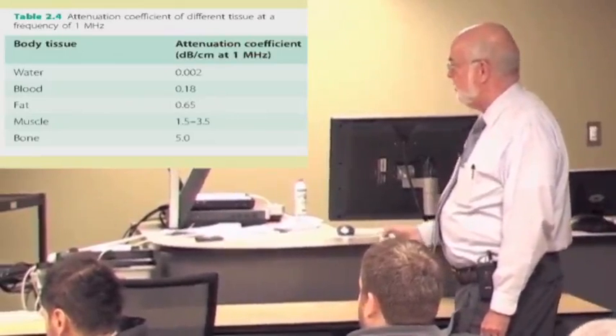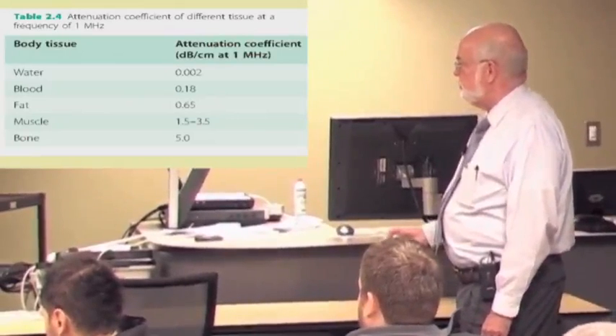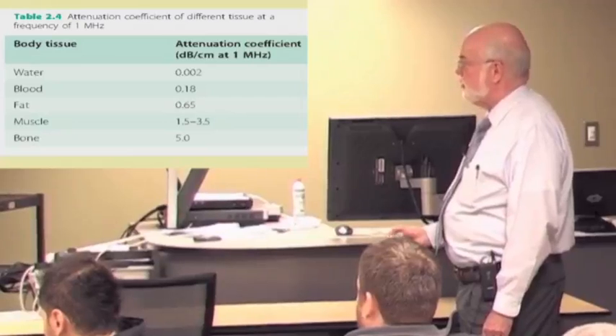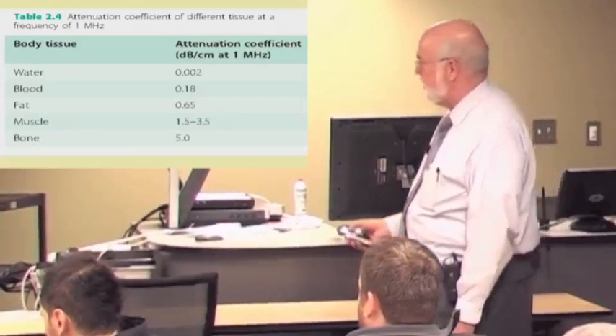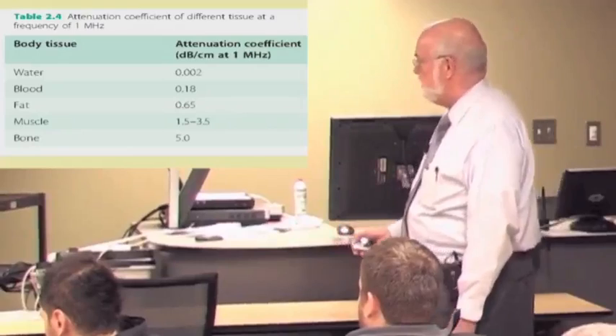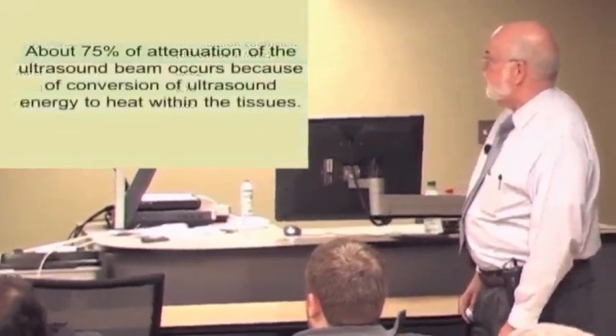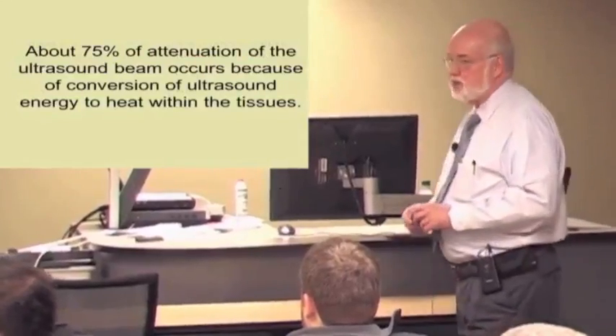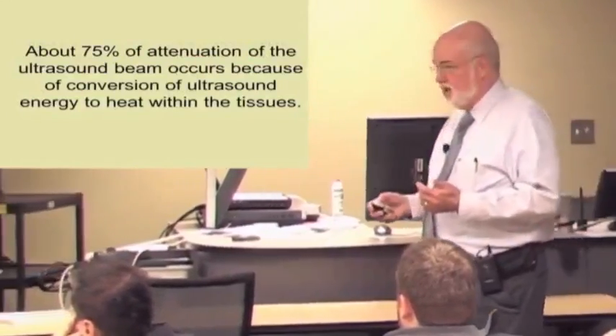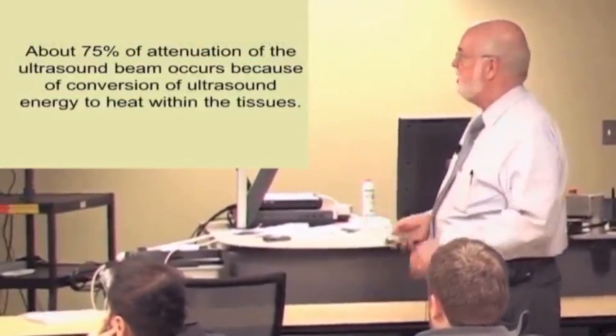And if you try to go through bone, there's a huge amount of attenuation. This is in decibels per centimeter at 1 megahertz. We usually scan at 3.5 or 4 megahertz, so actually you would end up with almost no energy getting past this structure back here. And again, we mentioned the fact that about 75% of attenuation is actually because we're converting this ultrasound energy into heat energy.